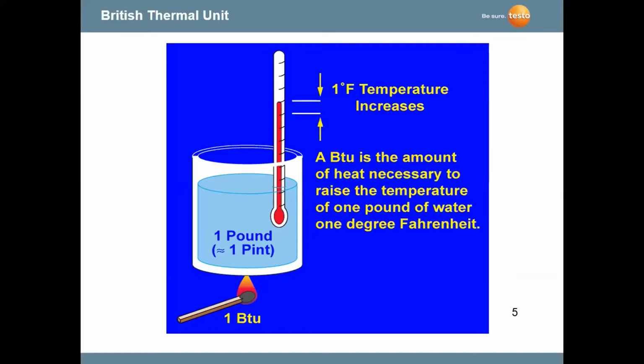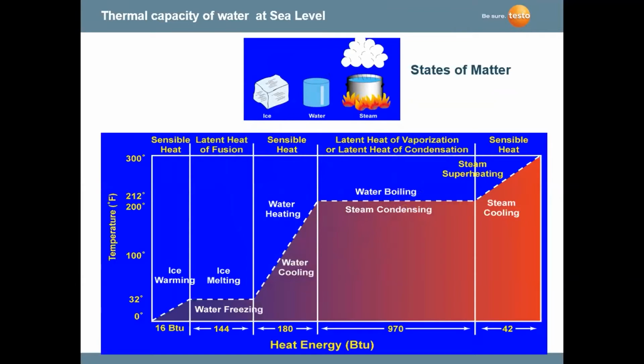BTU is the amount of heat necessary to raise the temperature of around 1 pound of water 1 degree Fahrenheit. So when we talk about BTU, we're really talking about energy to raise the temperature of water. So on this screen here, on the top, you'll see three states of matter: solid, liquid, and vapor or steam. And what this bottom chart represents is the change. And I use water. Water is very visual. We all know that water boils at 212 degrees at sea level. I assume that most places in Florida are at sea level.